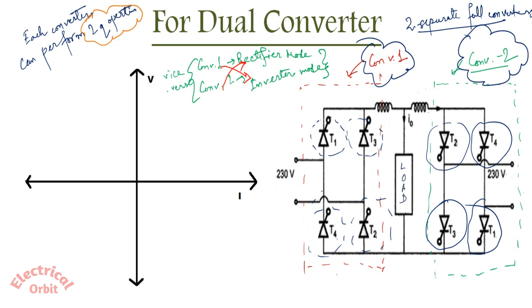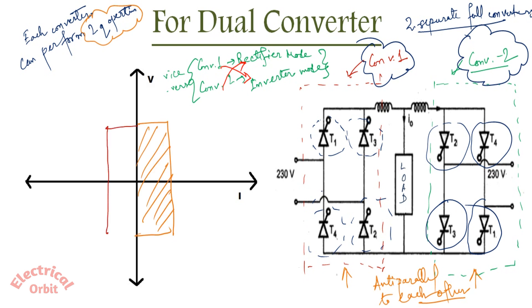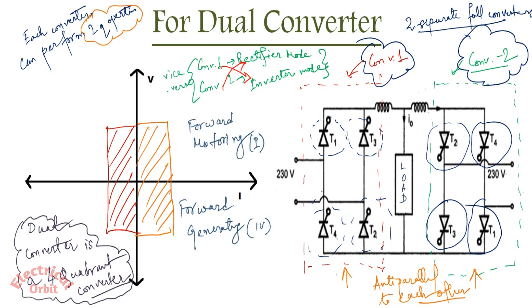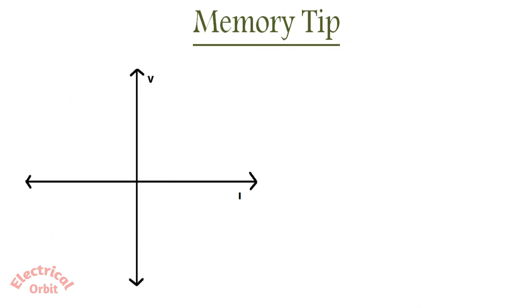The thyristors at converter 1 and converter 2 are anti-parallel to each other, so these two separate converters are not working at the same quadrant. If converter 1 can operate at quadrant 1 and 4, converter 2 operates at quadrant 2 and 3. So a dual converter is a four-quadrant converter where all four modes are available: forward motoring, forward generating, reverse generating, and reverse motoring.